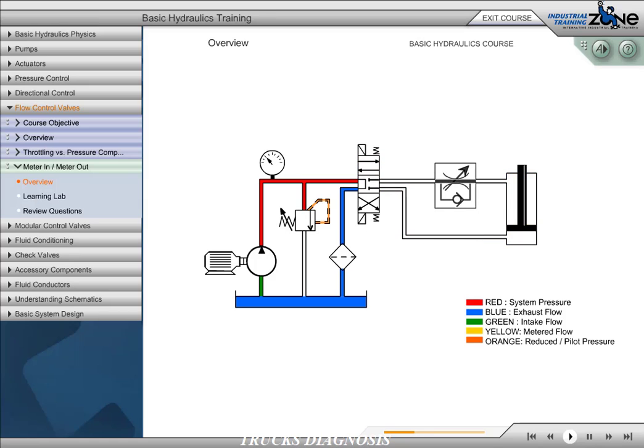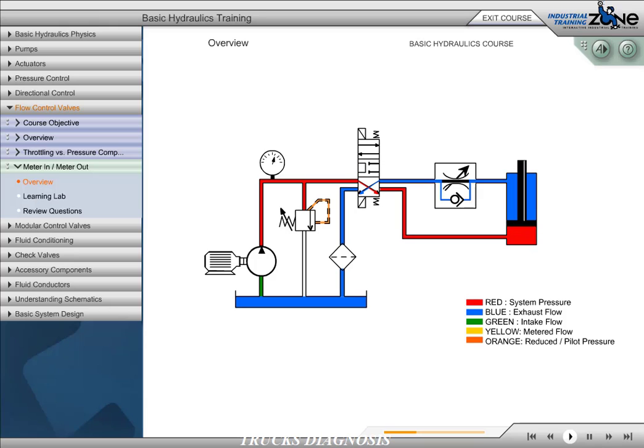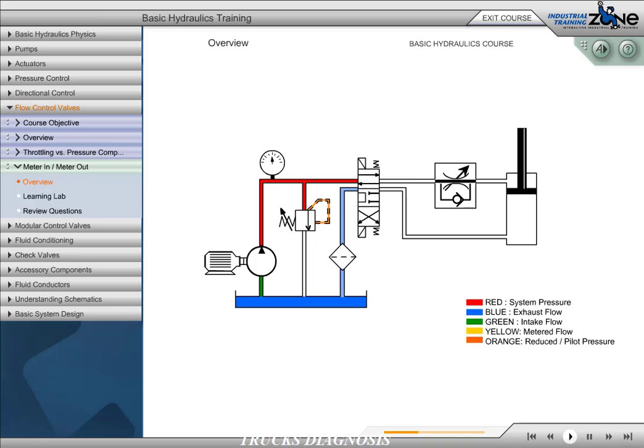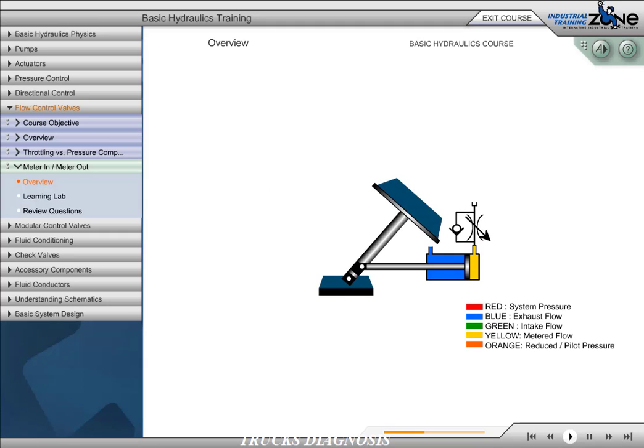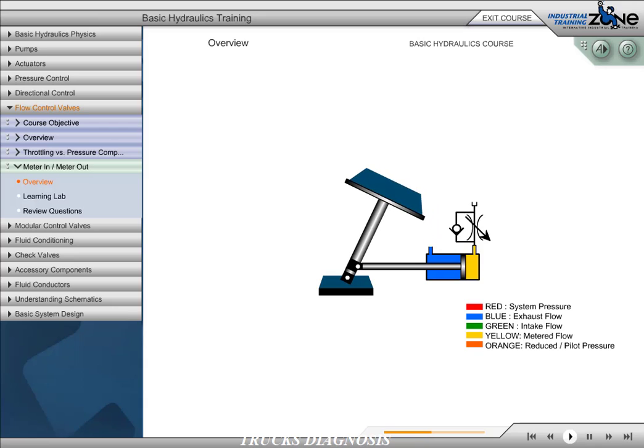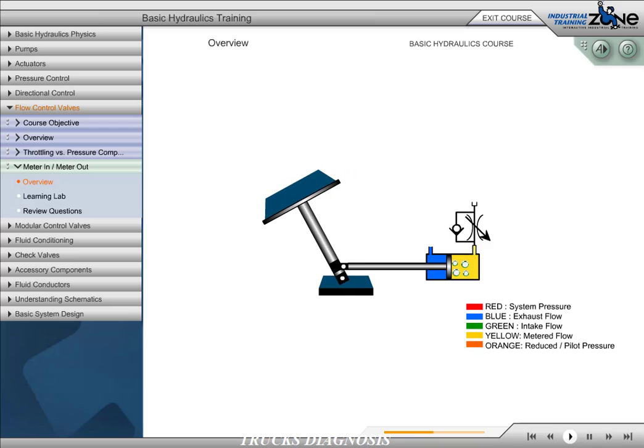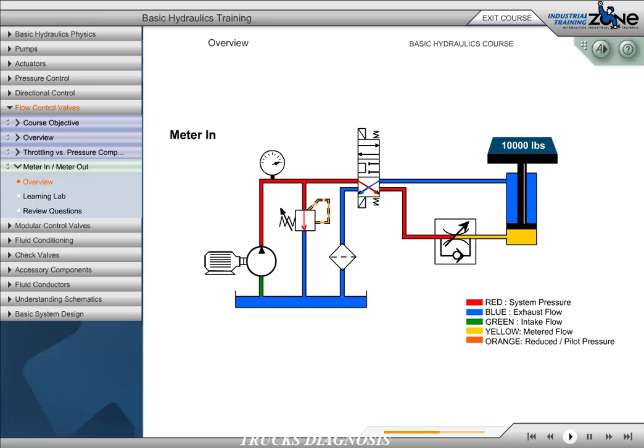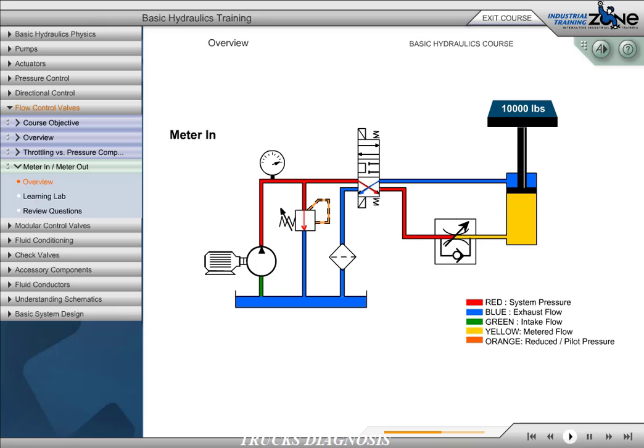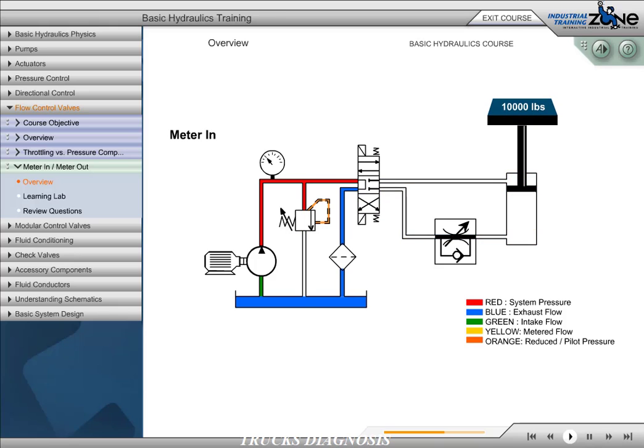When we move the flow control to the other line, the cylinder extends at an unrestricted rate. We can restrict the flow to the cylinder so that it will retract at a reduced rate. The advantage to meter-in is that it is very accurate with a positive load. However, when the load goes over center, the load becomes negative or overrunning. The load is no longer being controlled by the cylinder. As the load overruns, it causes the cylinder to cavitate. Although meter-in is usually the best placement for controlling a constant speed because it also dampens flow and pressure transients, it may be required in some applications to meter out.